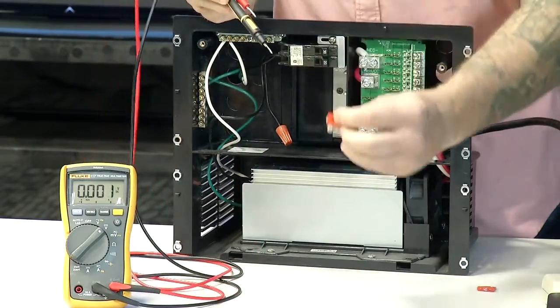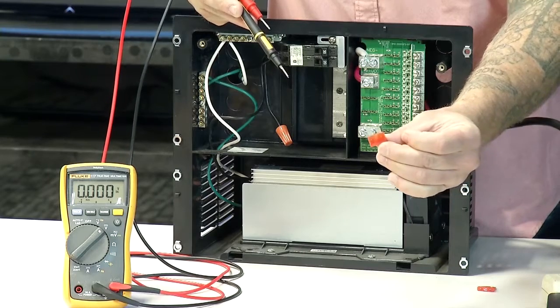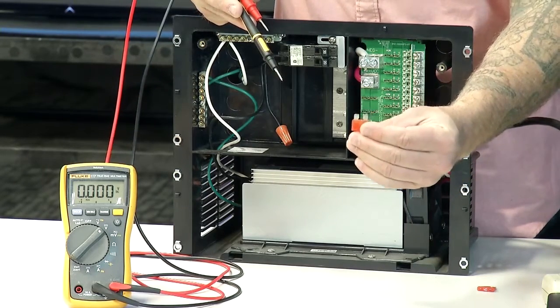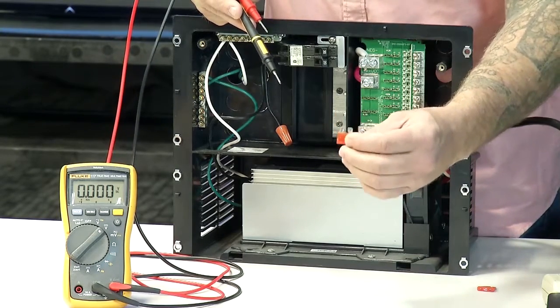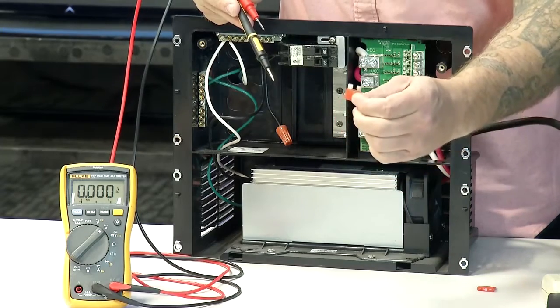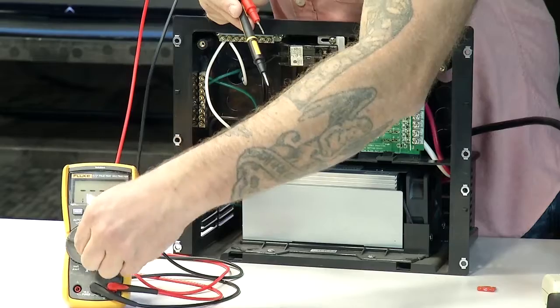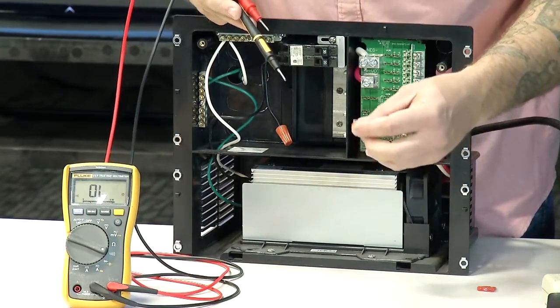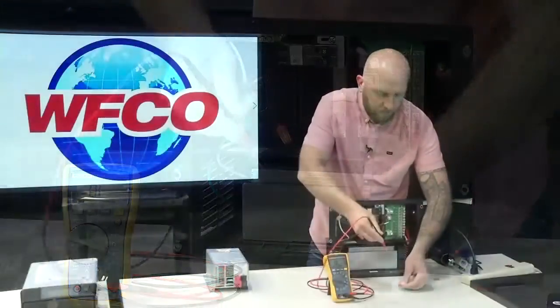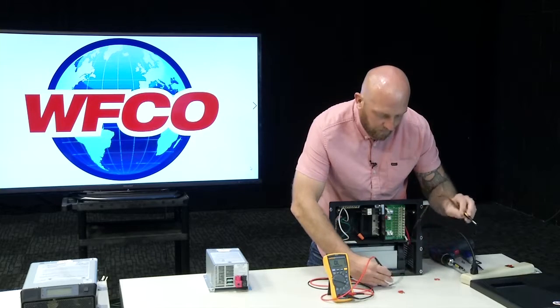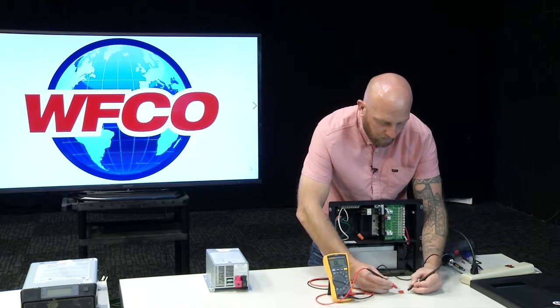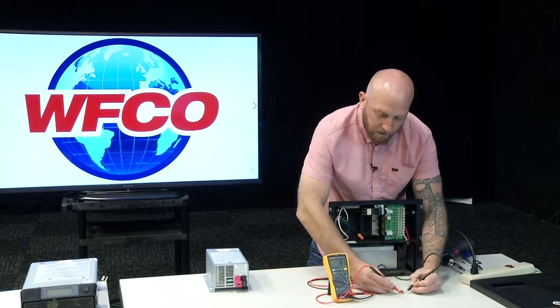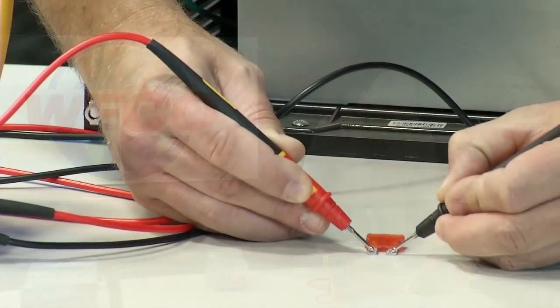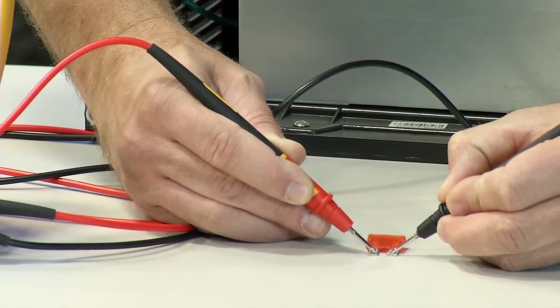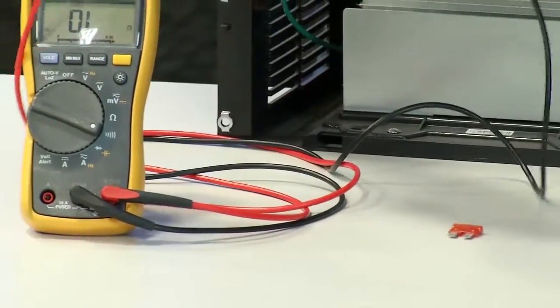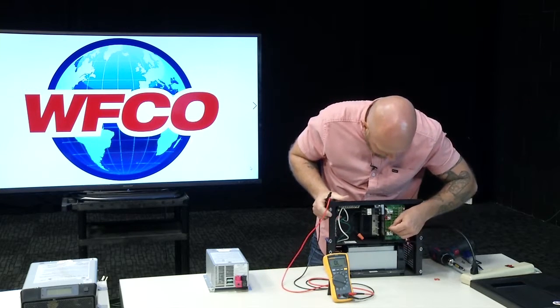To check your fuses, on my meter I have a continuity check, which looks like a sideways Wi-Fi symbol, but you can also ohm it out. You want to set it to 2000 ohms, and a good fuse should read out about 0 ohms. I'm going to turn my meter to continuity. Again, that's a sideways Wi-Fi symbol, and I'm just going to go across both blades of the fuse. On continuity on my meter, you'll get an audible buzzing, and it should be reading 0 as well. So 0 is indicating a good fuse. So I'm going to go ahead and insert those two 40 amp fuses back into the power center again.